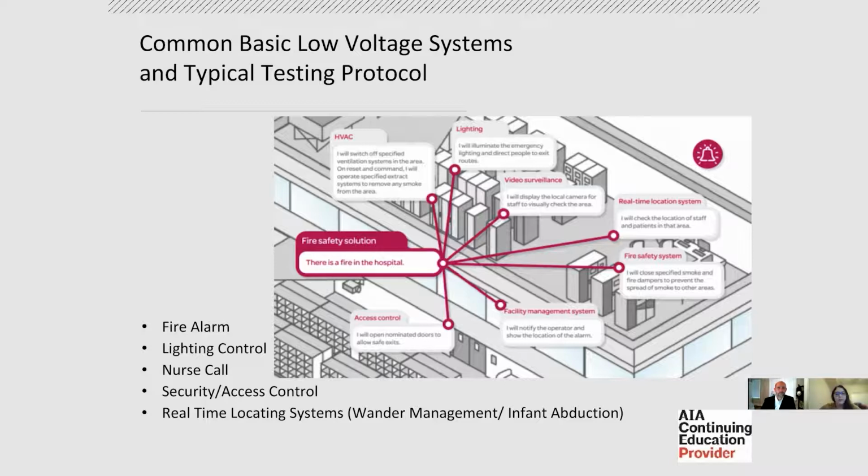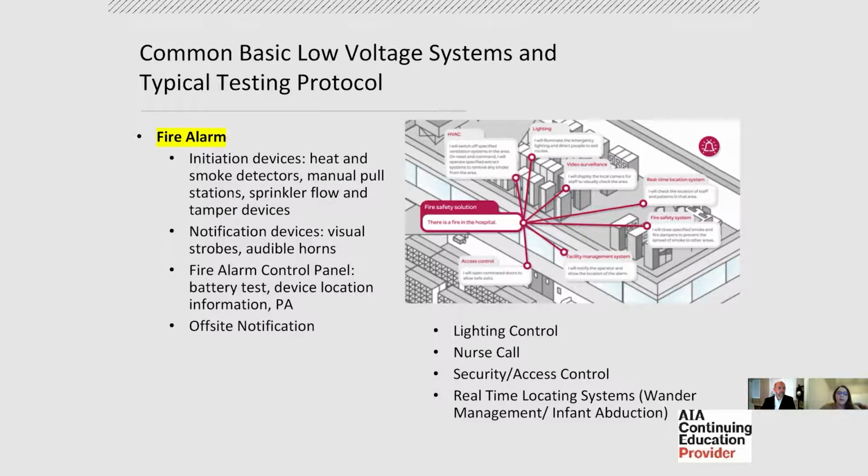We have some notification requirements provided in the NFPA 101 that apply specifically to healthcare. There are some unique caveats in the healthcare industry that the NFPA has addressed. Smoke detectors that are used to automatically open doors must sound an evacuation alarm, where other occupancies are granted an exception to that. You have the caveat of notification devices in critical care areas, where they're permitted to be visual only, making sure that you're not alerting babies or very critically injured patients of issues. Then also initiation devices for kitchen areas are not required to trigger building-wide notification in hospitals.